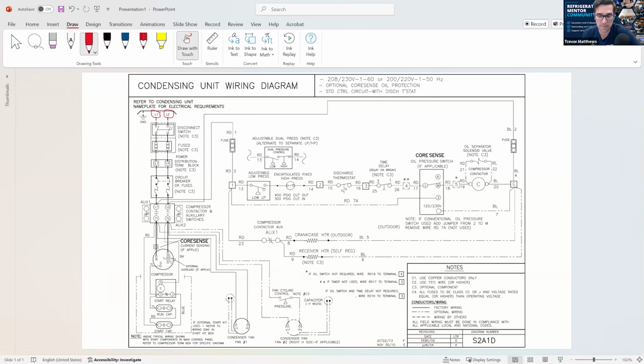The first step, and I do this in tons of my trainings, supermarket trainings, or even my compressor trainings, I talk about when we're doing electrical troubleshooting, you've got to get the wiring diagram and have it there. Over time, you get better and better at it, but it doesn't matter the system. The best technicians will get the wiring diagram. Unless you've worked on that system even 1,000 times, you know the wiring diagram inside and out. You can draw the wiring diagram.